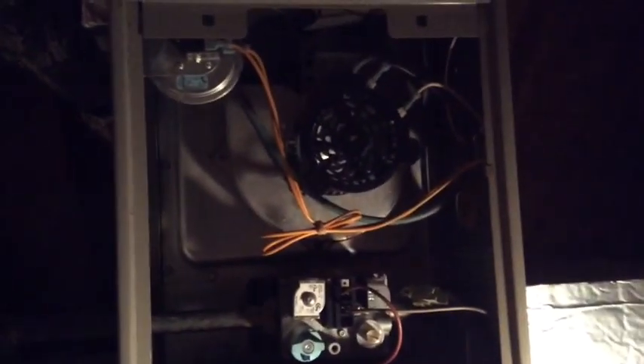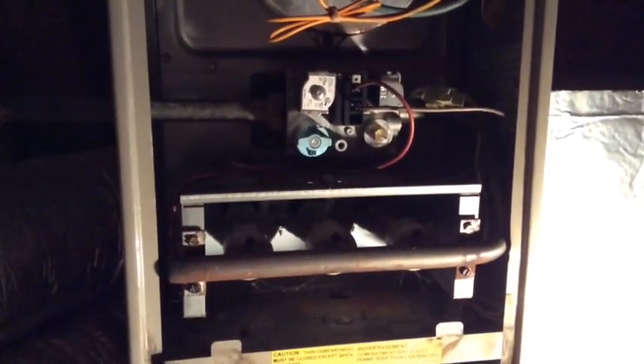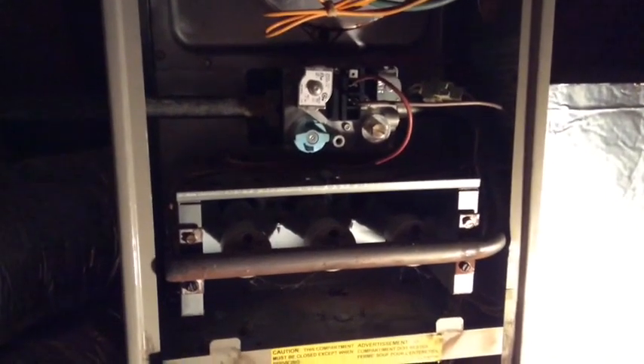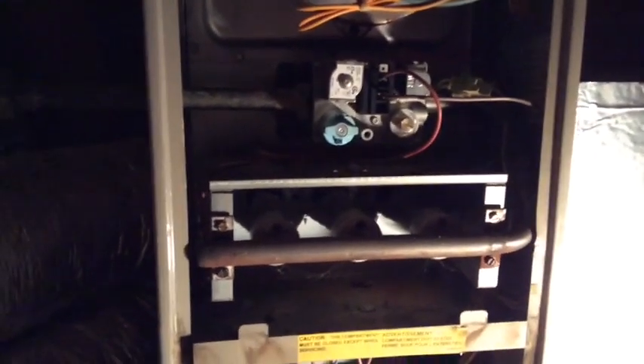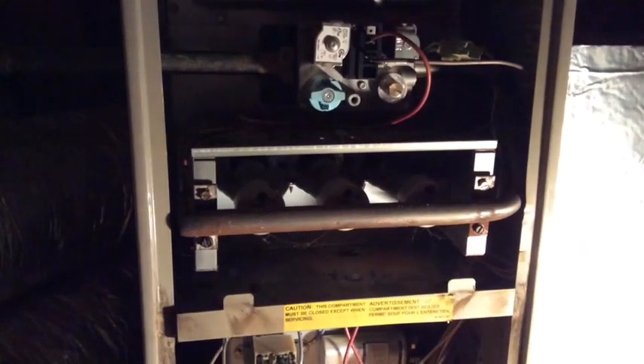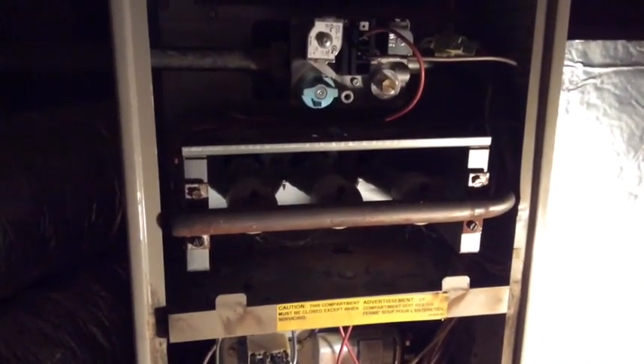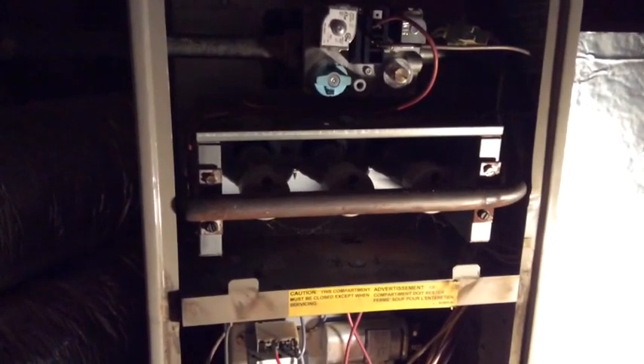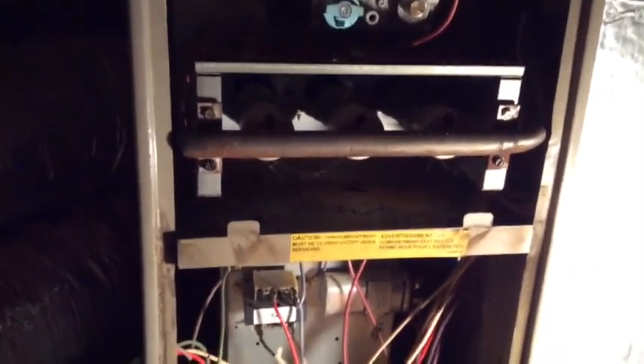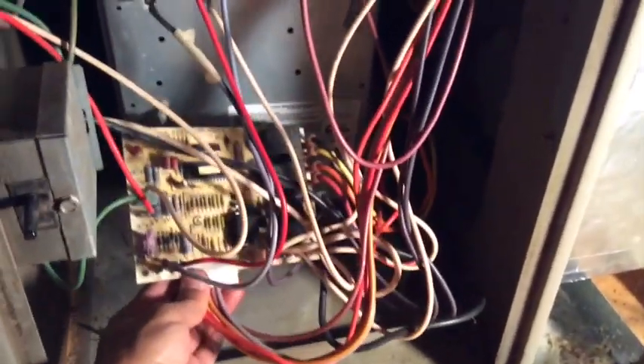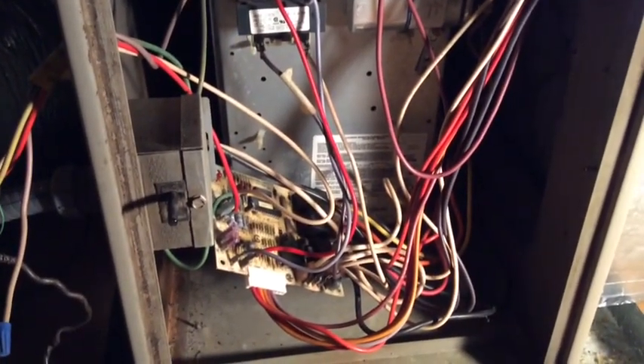What it was doing was, first, the purge fan was coming on, then the hot surface igniter was coming on about half the amount of time that it does on the operating furnace, and then the whole unit would shut down without ever opening the gas valve. There was never voltage to the gas valve, and there were no error codes on the LED for the control board for the unit. So I've determined that the board is bad.